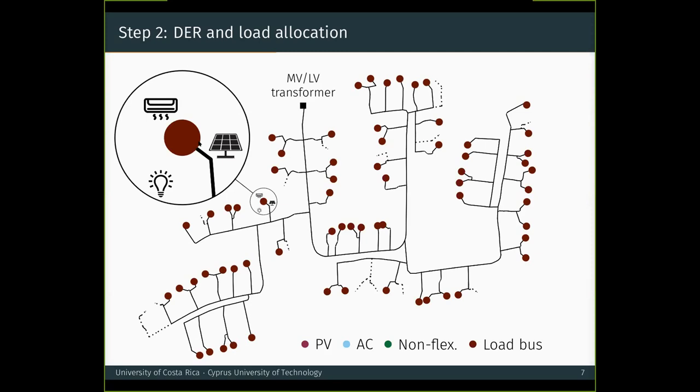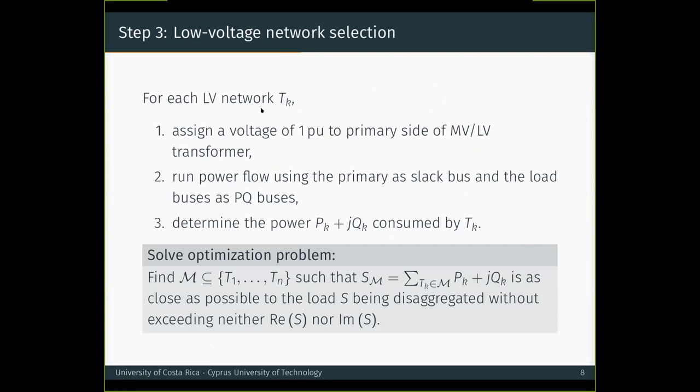After this allocation, we can therefore estimate what will be the consumption, the total consumption of each network, and use that estimate to select which of the available networks will be used to disaggregate a load, and we do that in the third step. For each low voltage network, we assign a voltage of one per unit to the primary side of the step-down transformer. Then we run a power flow using the primary as a slack bus and the load buses as PQ buses, and finally we determine the power consumed by that network. It is true that these networks will not operate in general at a voltage of one per unit when they are connected to the rest of the system, but this assumption is useful to know which networks to choose in the first place.